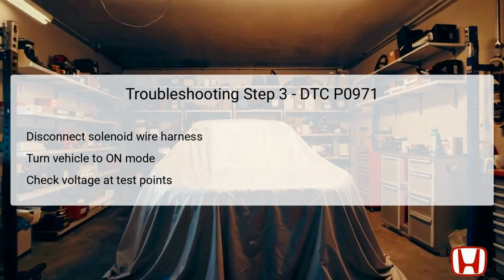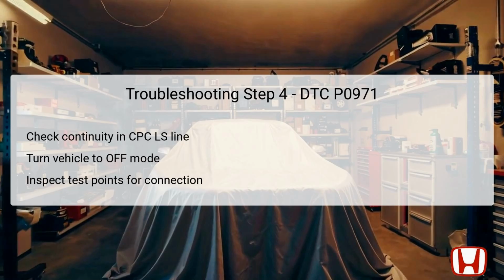If you find voltage present at the test points, this confirms that there is indeed a short to power in the line, and repairs or replacement of the damaged wiring will be necessary. Conversely, if no voltage is detected, the CPC-LS wire is likely intact, and you can move on to the next step. Step 4 requires an analysis of the continuity of the CPC-LS line.